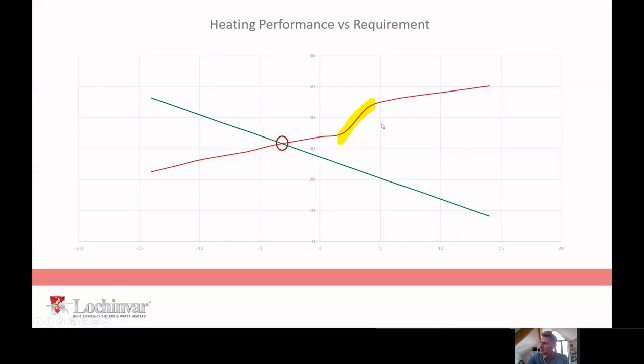And just before I go on to the next slide, I always like to point this bit out as well. Between an outside air temperature of 4 degrees and 2 degrees centigrade, we get this sudden drop off in the performance of the heat pump. I mean, we've got quite a big crowd, so I'm not going to open it up to the floor. Usually I would, but we've got a great attendance. But the reason for this drop off in performance is because it's the first time the refrigerant inside an electric air source heat pump is going to be below freezing.